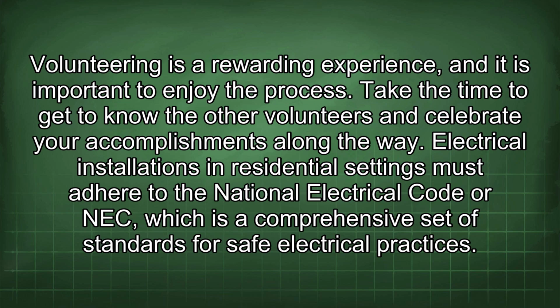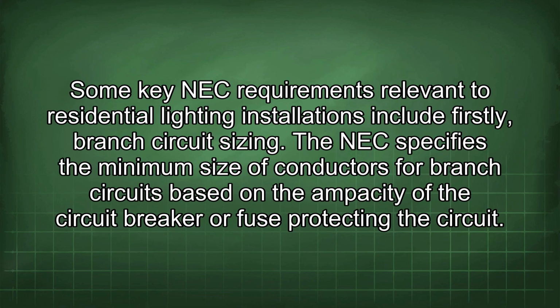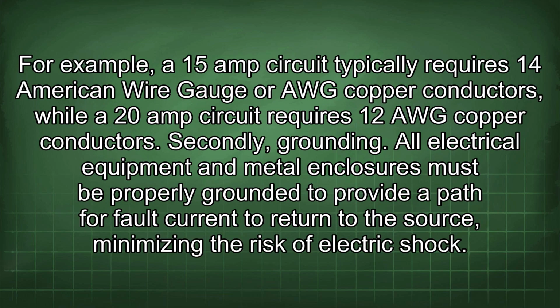Electrical installations in residential settings must adhere to the National Electrical Code or NEC, which is a comprehensive set of standards for safe electrical practices. Some key NEC requirements relevant to residential lighting installations include, firstly, branch circuit sizing. The NEC specifies the minimum size of conductors for branch circuits based on the ampacity of the circuit breaker or fuse protecting the circuit. For example, a 15-amp circuit typically requires 14 American wire gauge or AWG copper conductors, while a 20-amp circuit requires 12 AWG copper conductors.